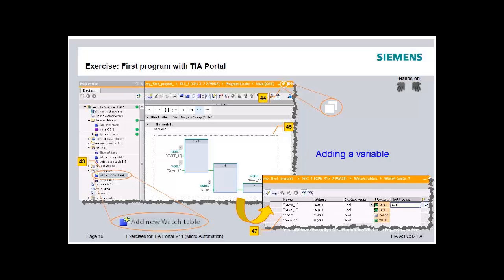Create a new watch table in the project tree. Open the watch table window using the plus button. Using drag and drop, select the elements in Network 1 and insert them into the watch table. The values for Start 1 and Stop can be entered in the modified values column. Modified values are sent to the controller as needed.